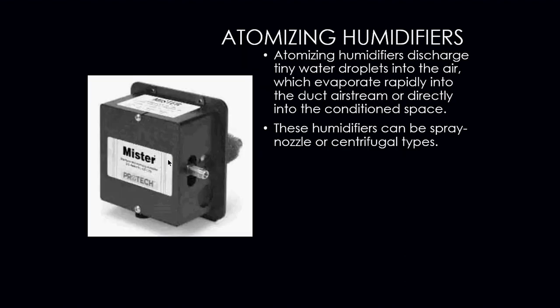Okay, your atomizing humidifiers, they're going to discharge tiny droplets into the air, which evaporate rapidly into the duct airstream or directly into your conditioned space. And these humidifiers can be spray nozzle or some sort of centrifugal type. So we have many different forms and many different ways to introduce moisture into a space. But one thing that every single one of our humidifiers that we have discussed so far has is that they all are controlled by some sort of humidistat.